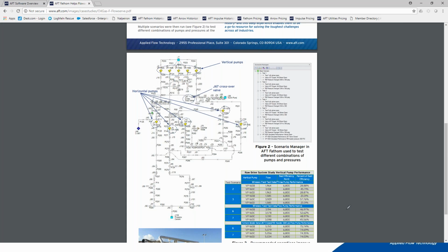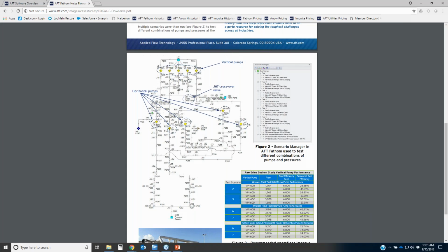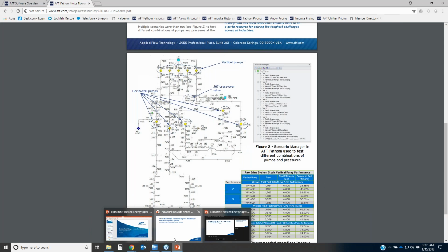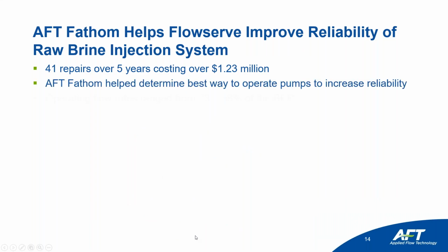In their final case, what they found was by operating these 2 pumps under various conditions right here at a time, their flow rates were able to match a lot closer to their best efficiency point flow rate. So they went from essentially as low as 23% up to about 75% of the best efficiency point. We're going to talk a lot more about that for the rest of the webinar. So you can read more about that case study there, and these are just the highlights.